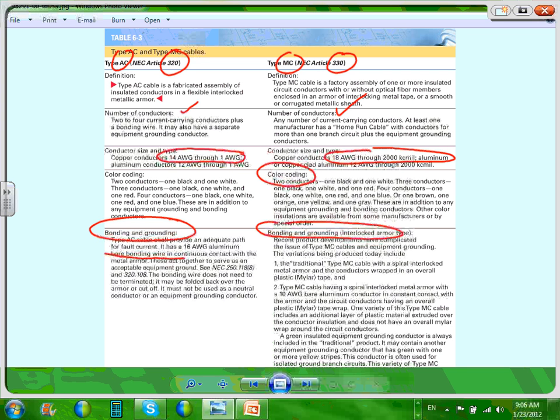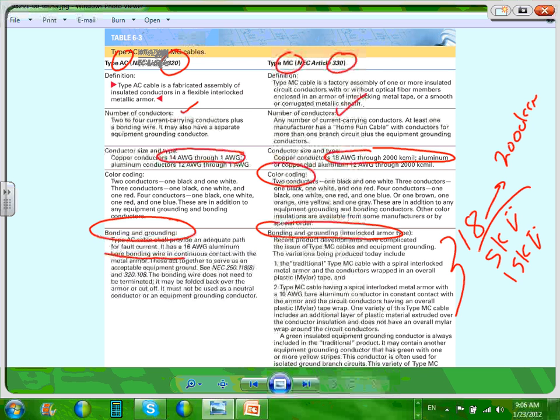What I like about the MC is you can get them from size 18 all the way to, as we said, 2,000 kcm. And you can get them 5 kV rated, 15 kV rated, I believe. So this cable, actually, my friend, MC cable: if I have a medium voltage conductor system, can I pull an MC cable for this? Yep, bring it on. Can I put an AC cable for this? No, there's no AC cable medium voltage. So that's where I want you, being an engineer, to think MC as we move forward into that cable.